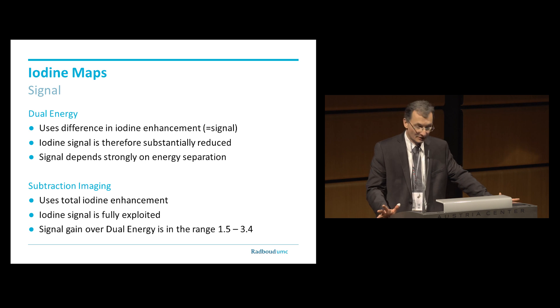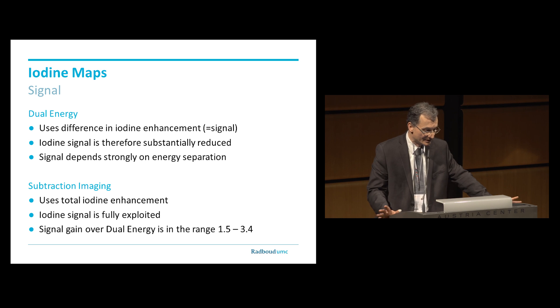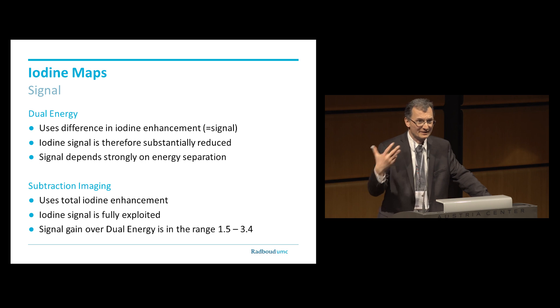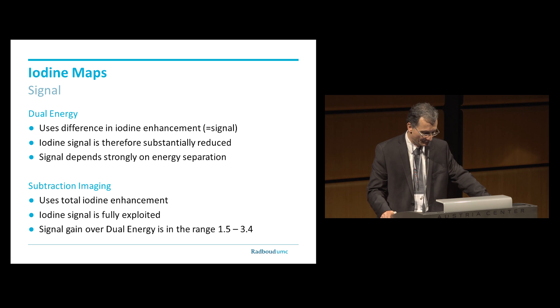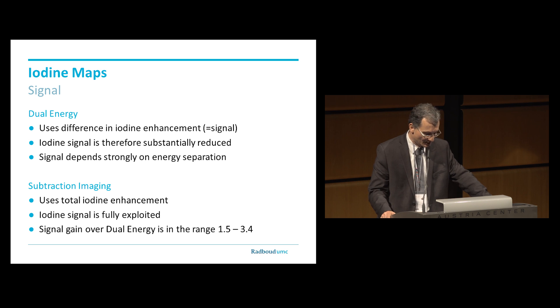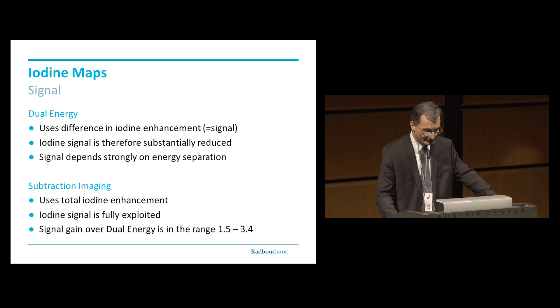To compare again: dual energy uses the difference in iodine enhancement, so the iodine signal is substantially reduced by the amount of the high KVP signal, and the energy separation is crucial. But in subtraction imaging, the signal gain is higher, but you need excellent spatial registration.